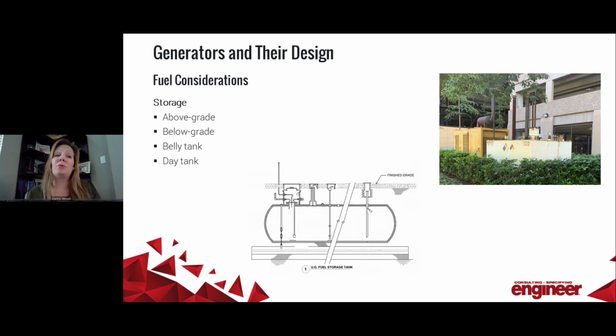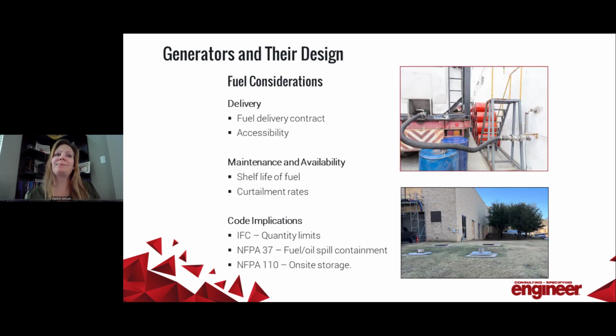If you're inside of a building, you typically will have a smaller standalone tank, which is what we refer to as a day tank. The above ground options could be this standalone tank that you see in the photo here, or it could be mounted directly under the generator, and we refer to that as a belly tank. So there's all different types of mountings for that on-site diesel fuel storage.